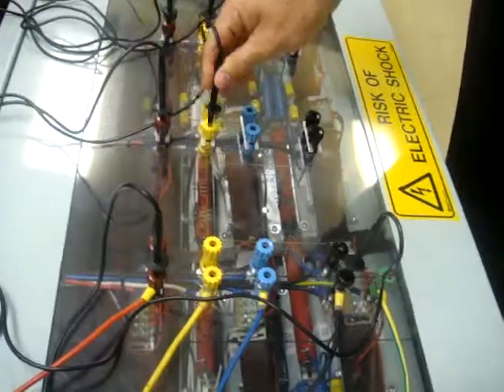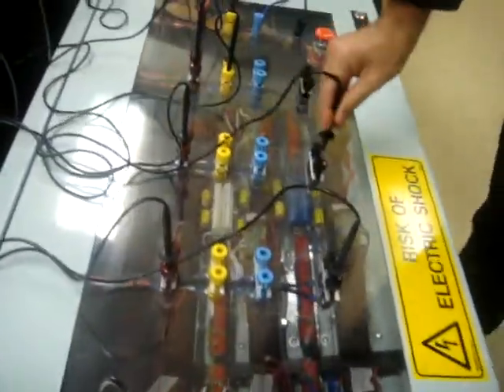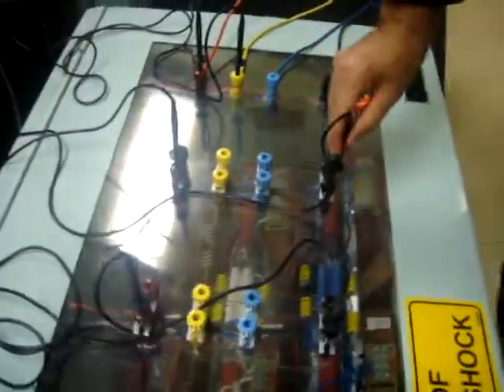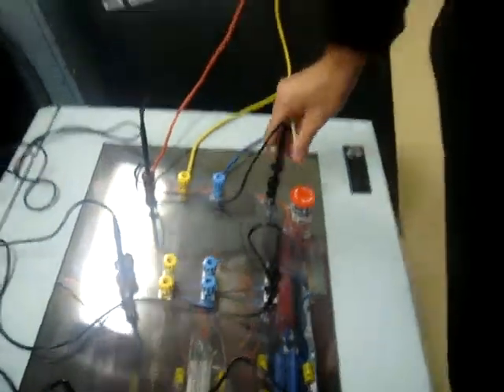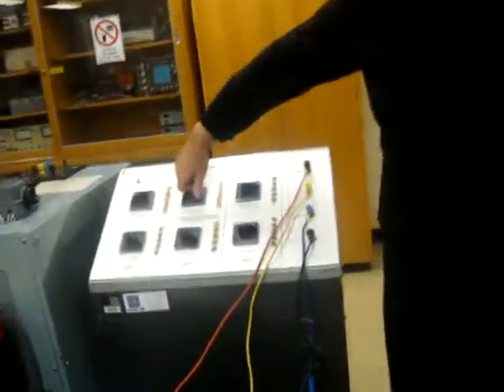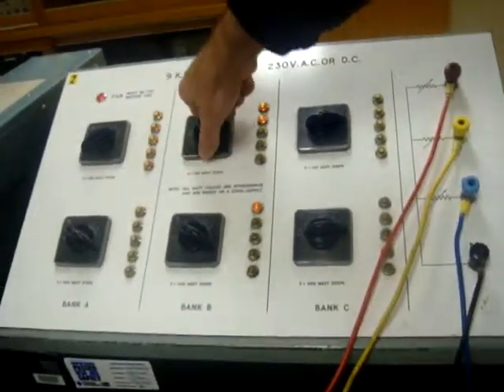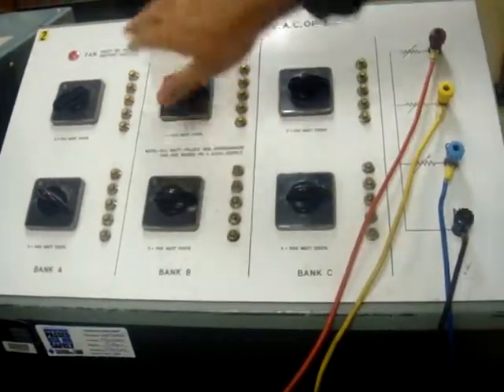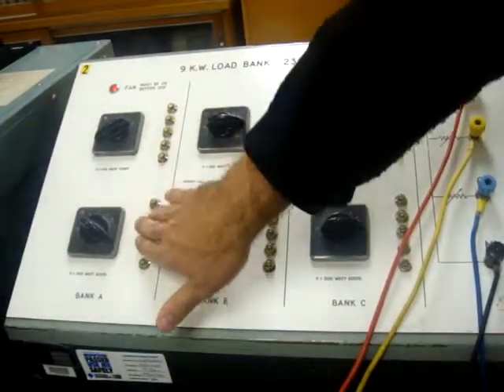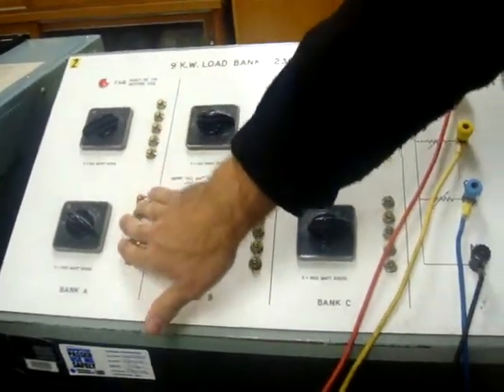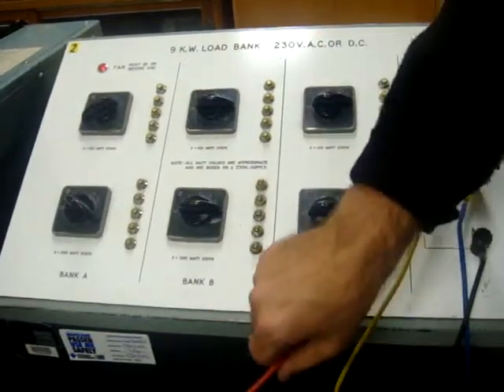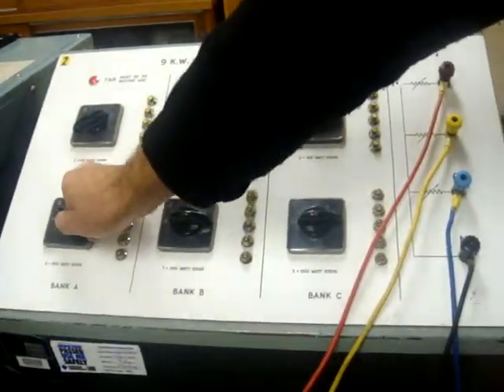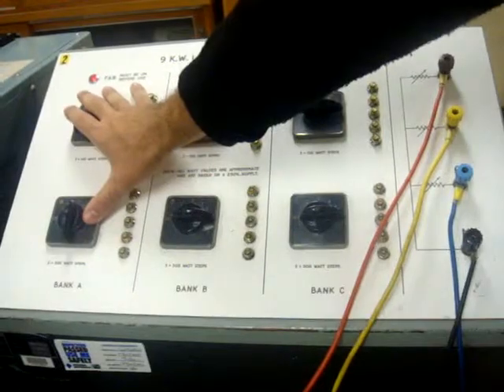Now, if we connect our power meters into a single phase configuration, we must first and foremost increase our yellow bank. We have 1 kilowatt through bank A, which is the red phase. Therefore, we must step it to 2 kilowatts.